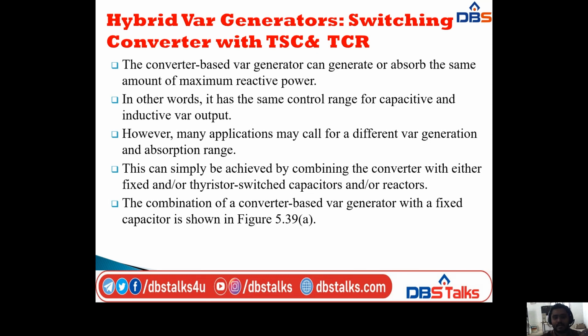However, many applications may call for a different VAR generation and absorption range. This can simply be achieved by combining the converter with either fixed or thyristor controlled capacitors or reactors, like the TSC and TCR. Firstly, I will take the combination of the converter based VAR generator with a fixed capacitor, that is FC.